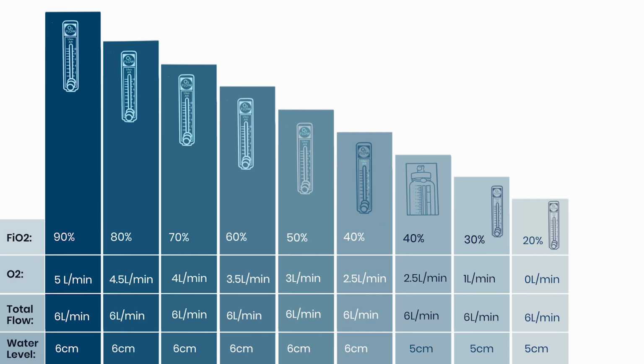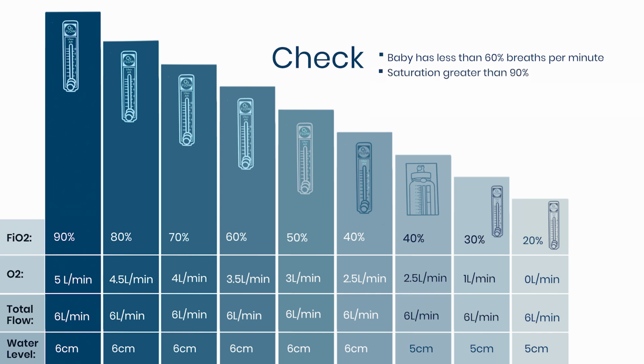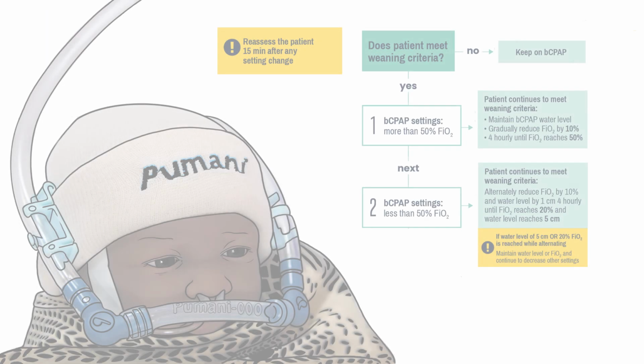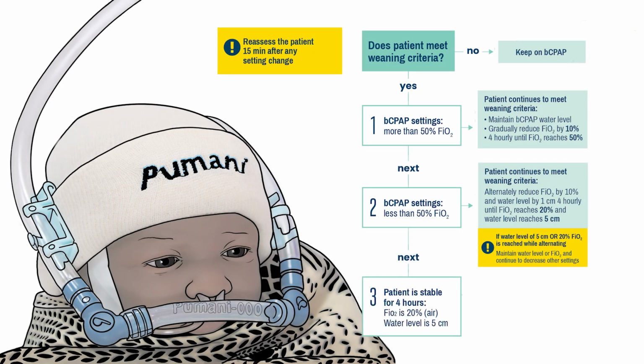When you reach the minimum settings, leave the baby for 4 more hours to make sure they are still stable. Check the respiratory rate is less than 60 breaths per minute. Their oxygen saturation is more than 90%, and they have no significantly increased work of breathing or other signs of respiratory distress. And then you are ready to take the baby off the machine.